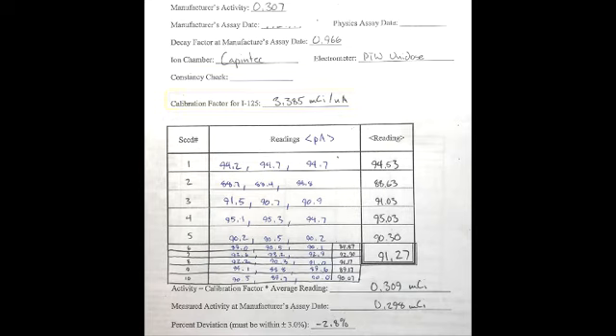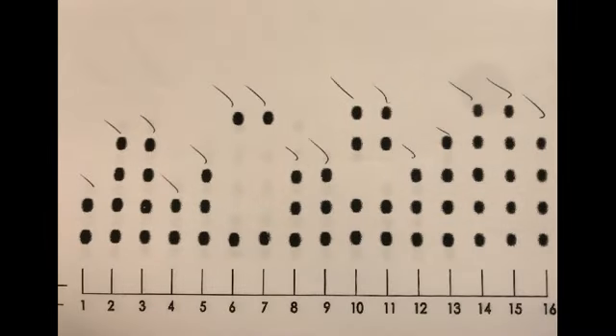So here's an example assay. You have to make sure the dates are right, of course. If the manufacturer assays on one day, and then you assay the seed 3 days later, it will have decayed, right? So you have to correct for that. Also, you want to verify the loading of the seeds in these needles if they're preloaded. So here is an autoradiograph where the needle lies against a film, and you get an exposure on the film, and then you can check the spacing between the seeds to make sure that it is correct.